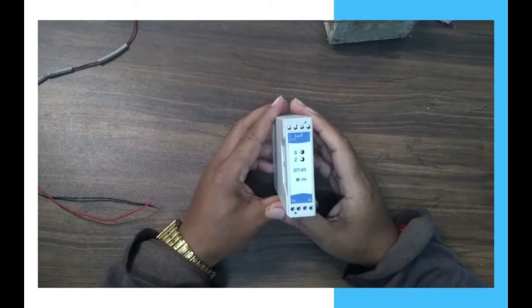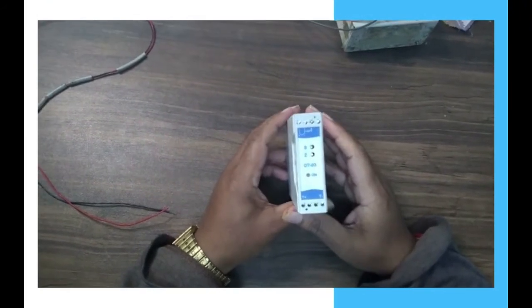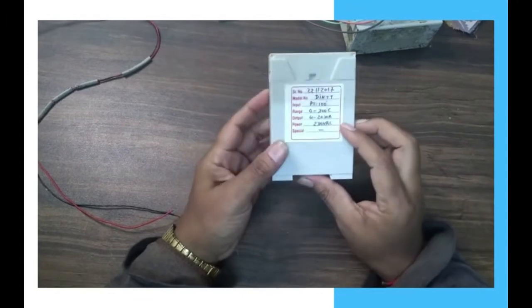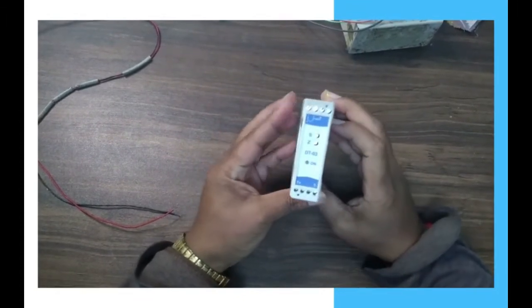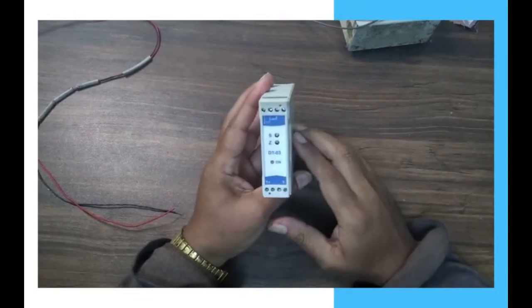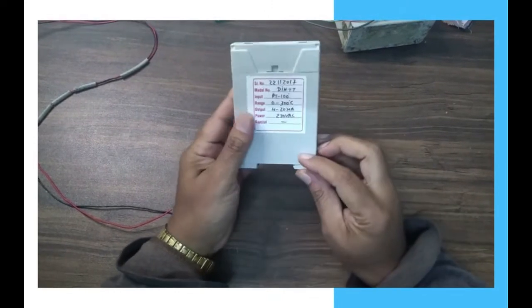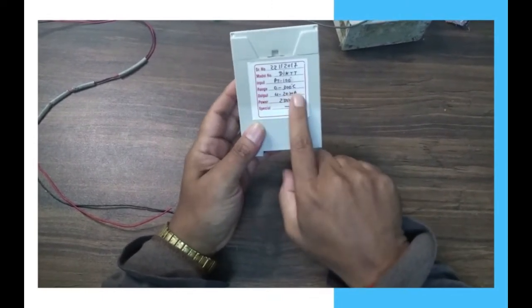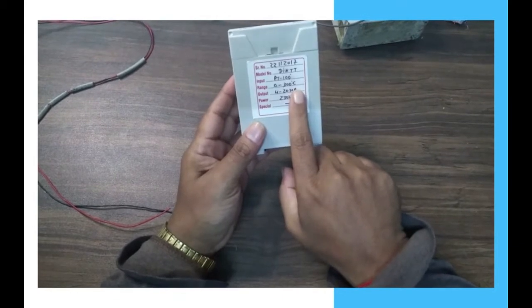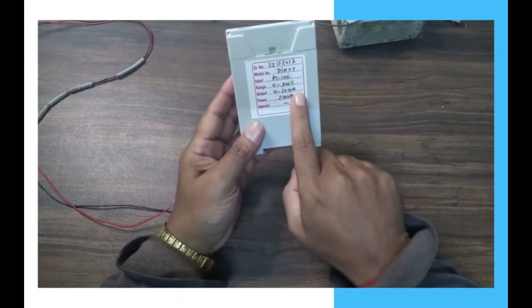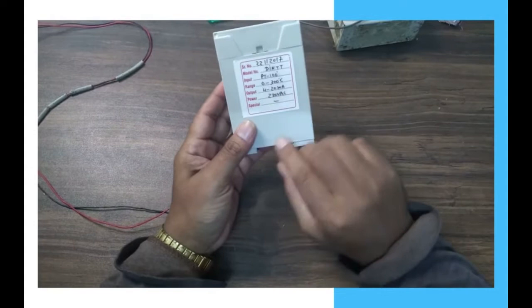Welcome friends. Today we are going to discuss the DIN rail mount temperature transmitter. This is how it looks here. Input is RTD 3-wire, temperature range is customized, output is 4 to 20 milliampere, and power supply is 24 VDC.